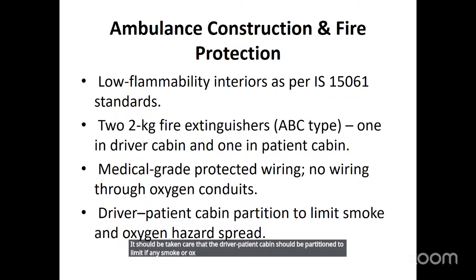It should be taken care that the driver and patient cabin should be partitioned to limit any smoke or oxygen hazard. So the next heading would be how to contain or restrict the oxygen system, and oxygen safety. So regulators should be approved. Most of the times in our setups, we see the regulators are broken. Jumbo cylinders and oxygen cylinders, even small cylinders, the regulators are not in place. We are just struggling and doing jugaad with the regulators. So those should not be there. Gas duct should be vented. Emergency oxygen outlet should be there, and minimum number of cylinders should be kept as per the safety standards.